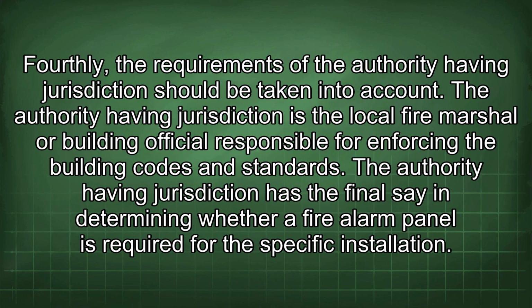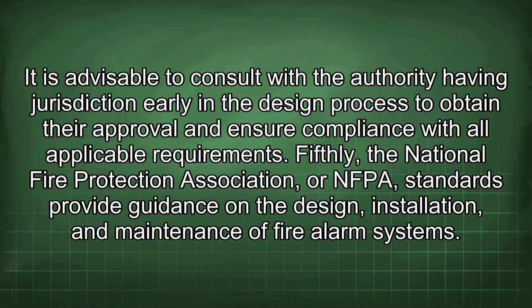Fourthly, the requirements of the authority having jurisdiction should be taken into account. The authority having jurisdiction is the local fire marshal or building official responsible for enforcing the building codes and standards. The authority having jurisdiction has the final say in determining whether a fire alarm panel is required for the specific installation. It is advisable to consult with the authority having jurisdiction early in the design process to obtain their approval and ensure compliance with all applicable requirements.